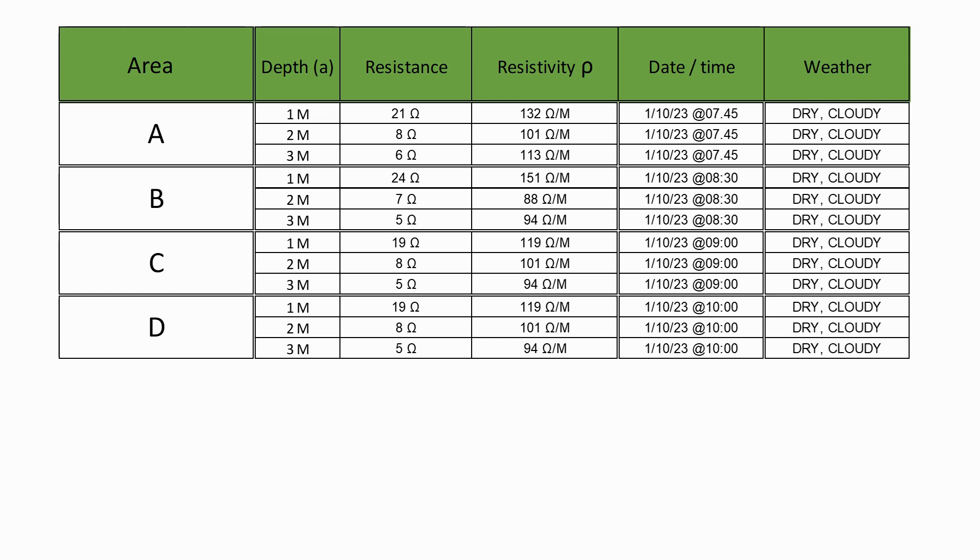We then take an average of the four readings at each of the depths. So to get the average soil resistivity value at a depth of 1 meter, we take the 1 meter readings measured at location A, B, C, and D, divide them by the number of readings which was 4, giving us an average at 1 meter of 130 ohm meters.